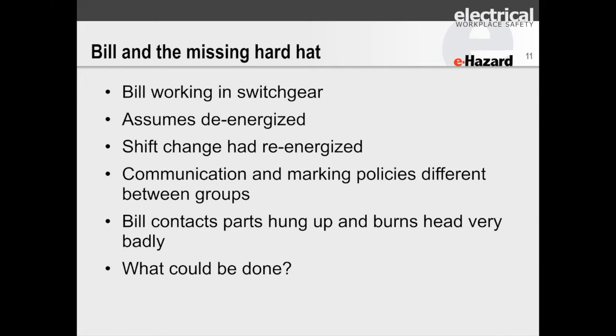Now, what could have been done there? Well, making sure that we have clear policies and procedures on re-energizing. The equipment should have been closed up and put back into its normal state, not re-energized. And there should have been a shift change job briefing to let people know what's changed since last time you were on. This company did require a shift change job briefing, but it didn't actually happen.